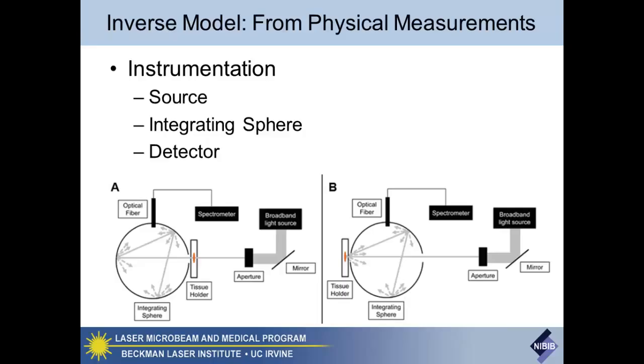Typical inverse adding-doubling setups have your slab of tissue. To make a transmittance measurement, you have your light source, collimate the beam, send it through your sample. Photons can be exiting at almost any angle, but if it's right up near the front of the sphere, the angles will bounce off the reflective surfaces of the sphere — this is a physical interpretation of integration. Out of all these angles, photons bounce within the sphere, and you have a detector at a small point that samples the relative intensity integrated out of all the photons that traveled through your sample into the sphere. It basically lets photons bounce around enough, kind of like isotropic scattering, so it forgets what the angular dependence is and integrates all that so you can measure it.